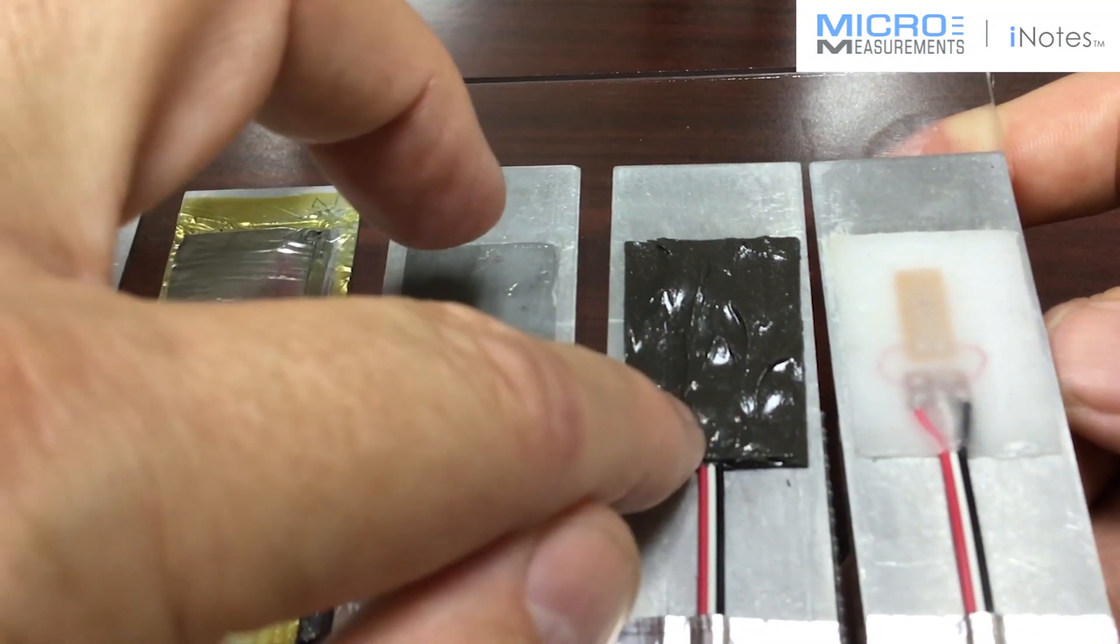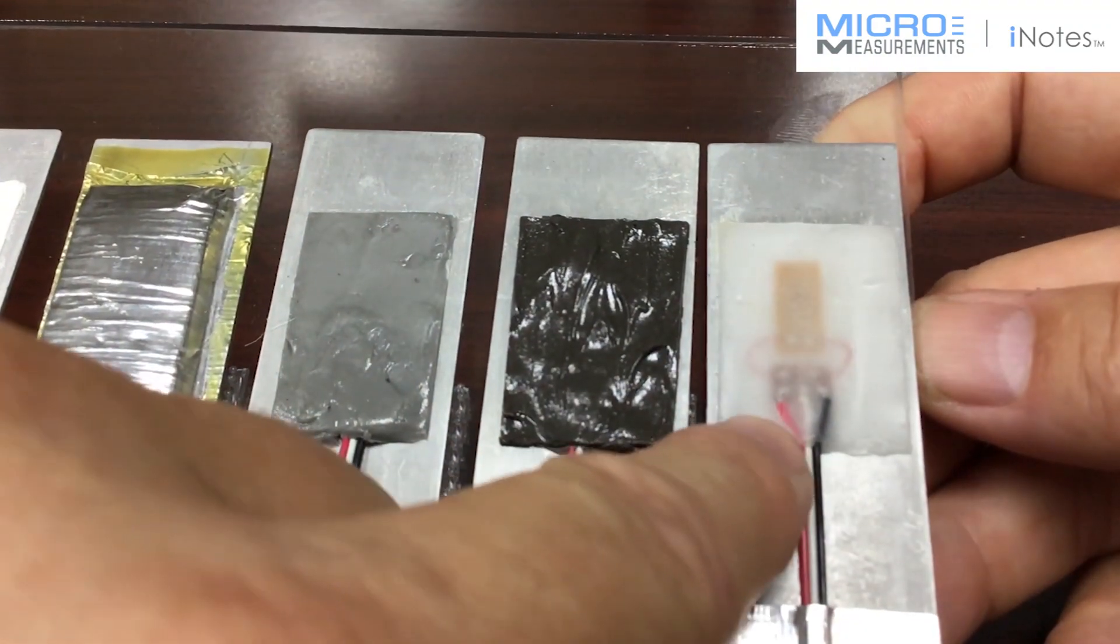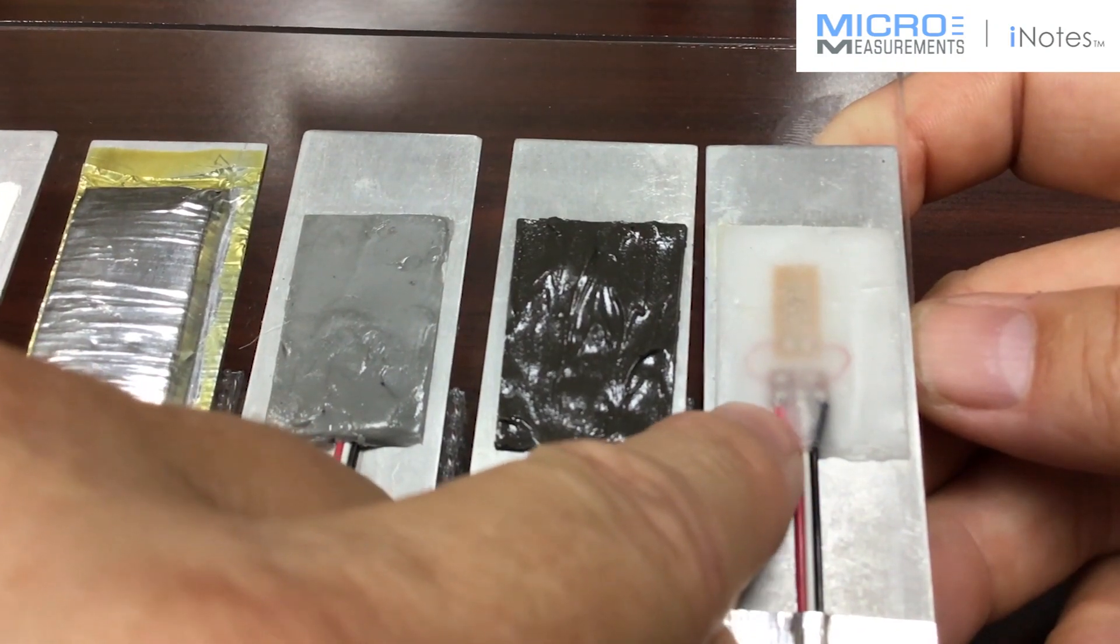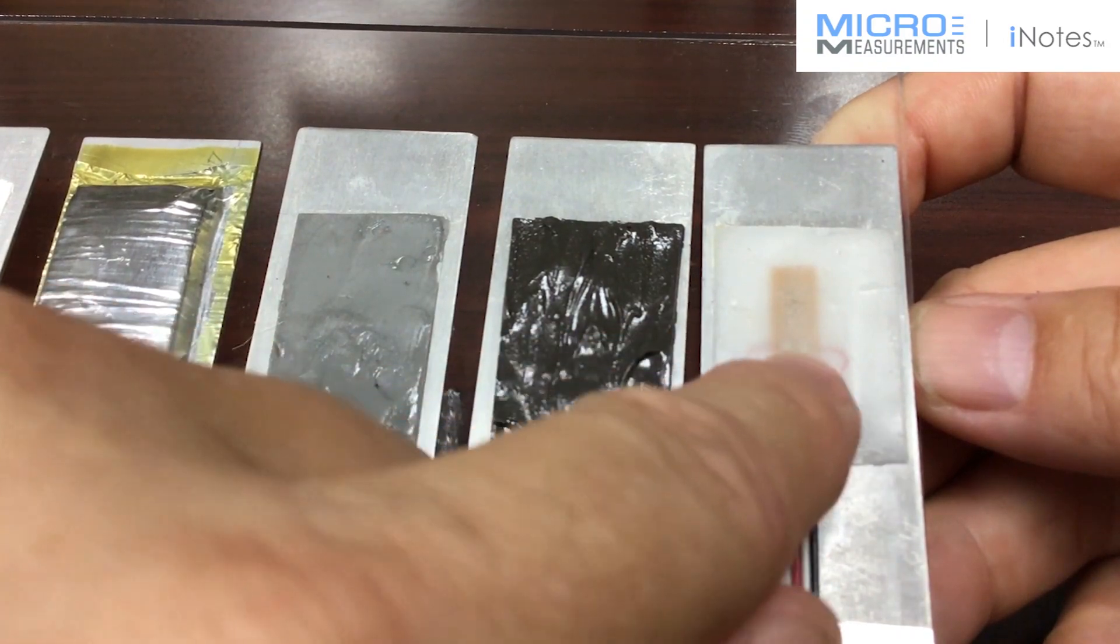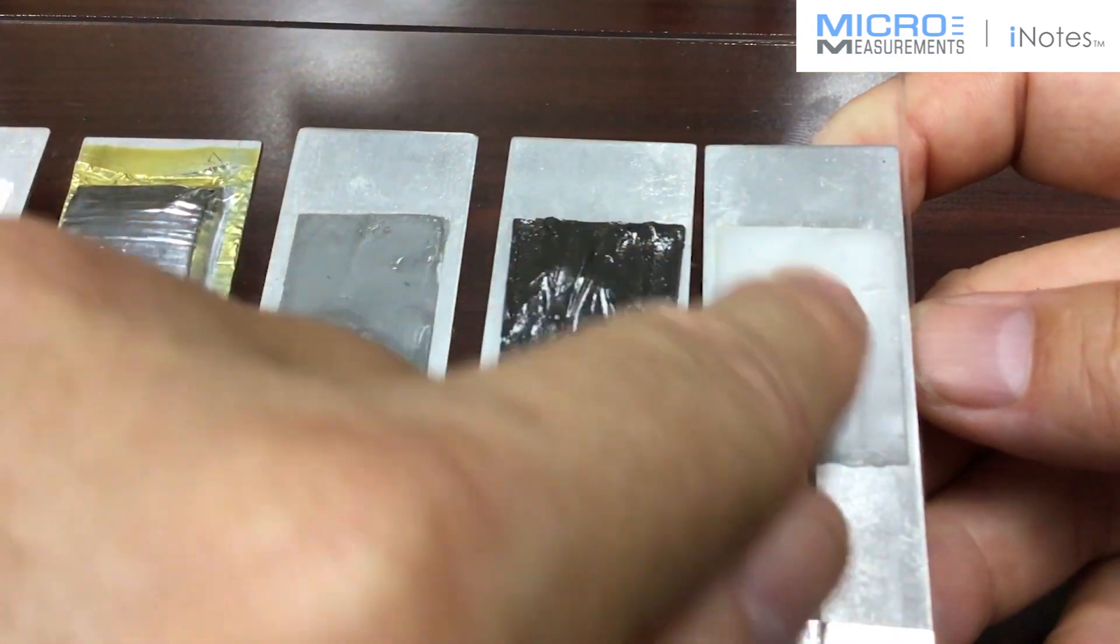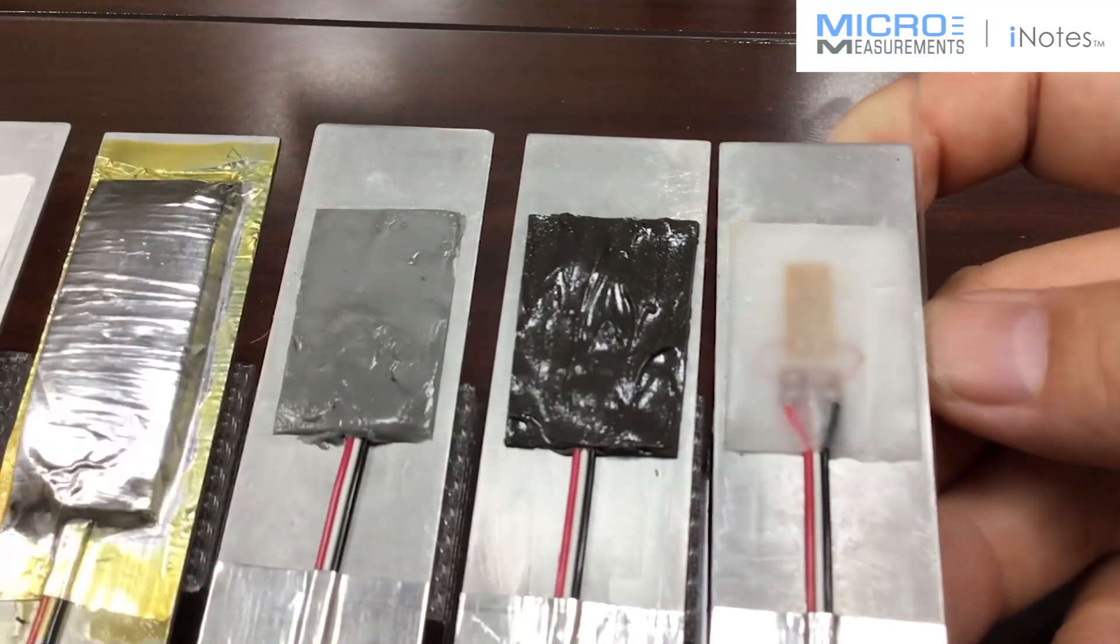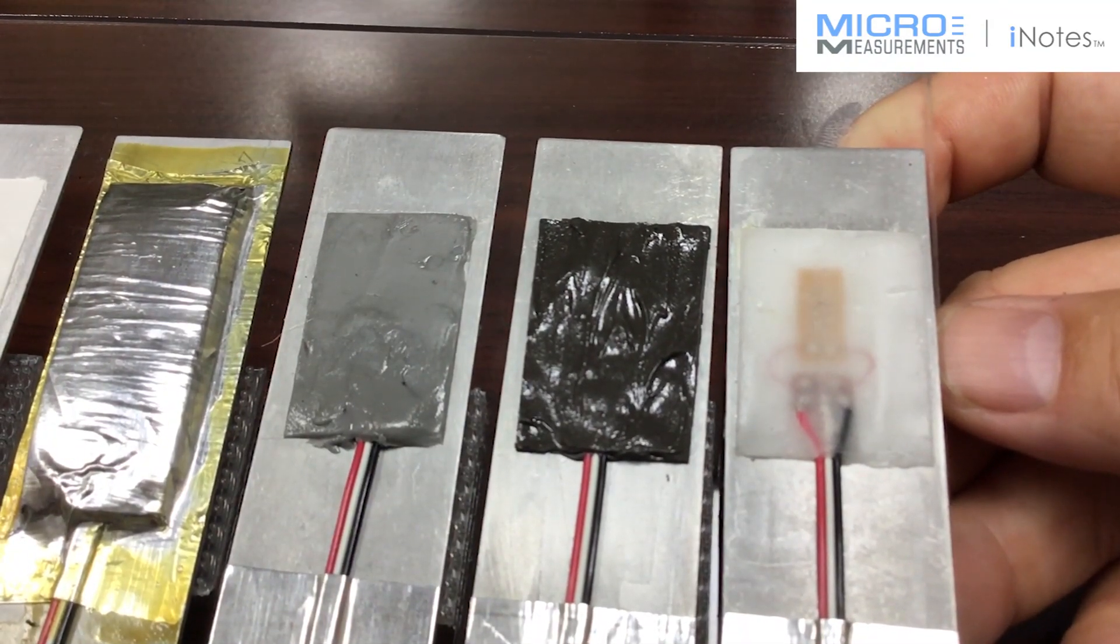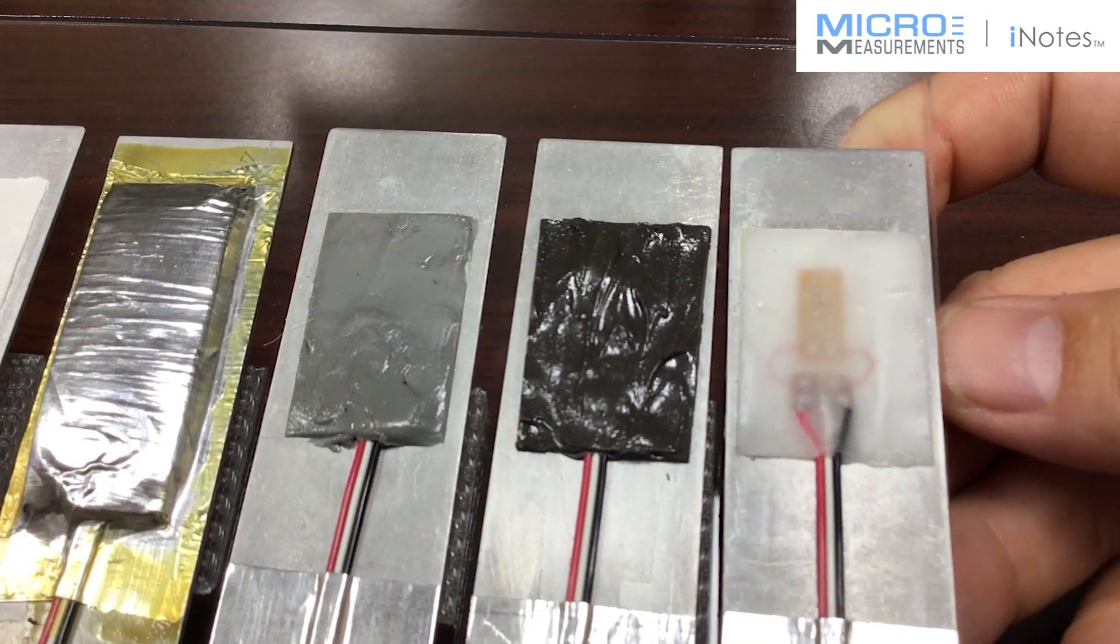And oftentimes it's used in combination with other coatings, and oftentimes it's used in combination with this last one which is our M-Coat W-1 Microcrystalline Wax. Wax is the best moisture barrier we've got, and oftentimes you'll put a coating of wax over top of the strain gauge and then you'll follow it with some M-Coat-JA, and that makes a really tough combination of a moisture barrier and mechanical barrier.